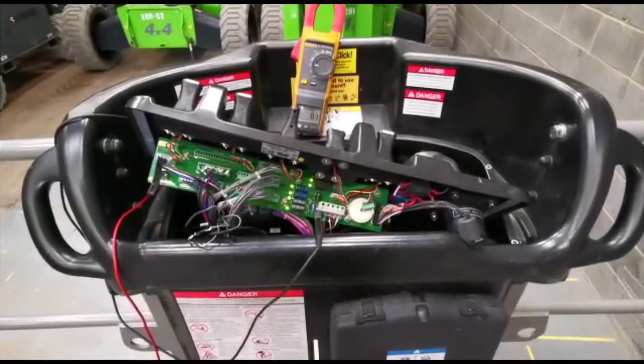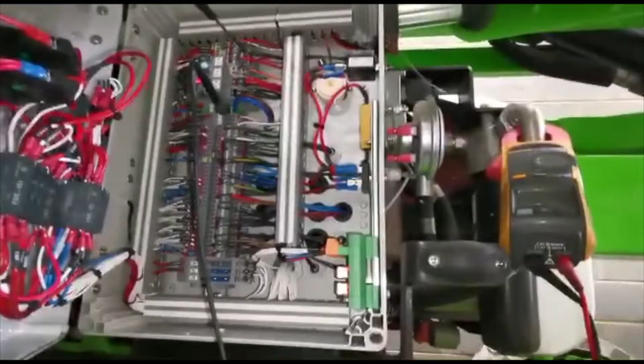So what I'm going to try is connect a diagnostic module to see if the cage weight is reading correctly, and then check the PLC plug to see if the connections are good there. Couldn't see any problems in the cage, it was reading 30%, meaning someone standing in it, so the cage weight system is working fine.